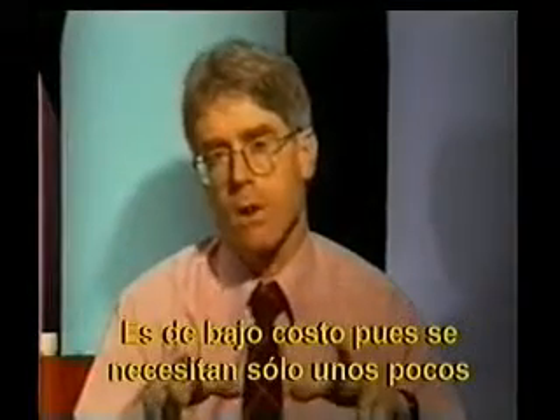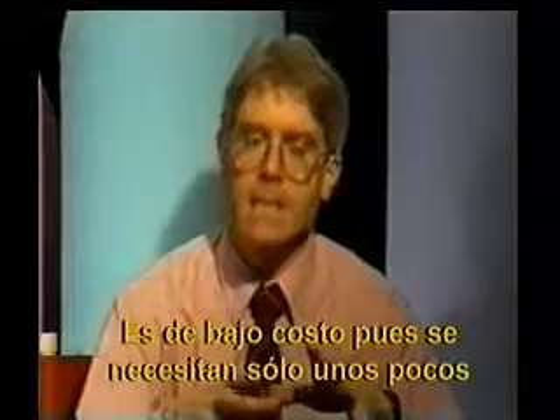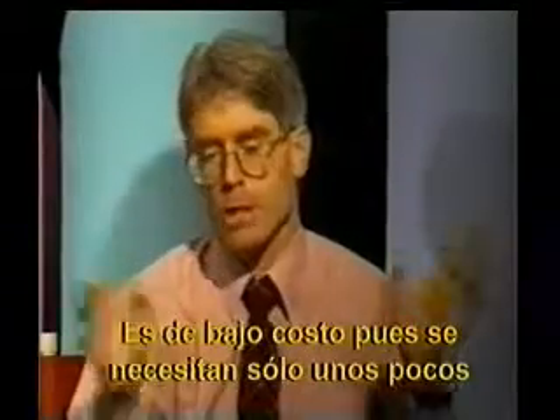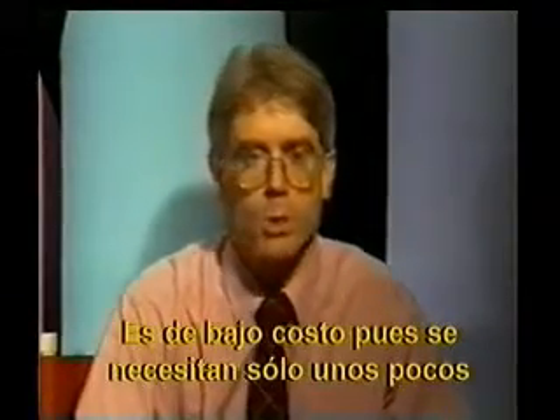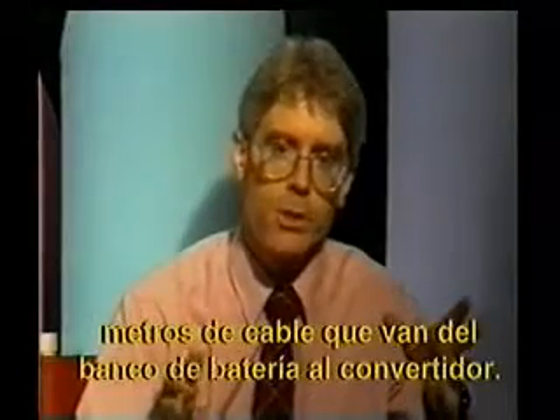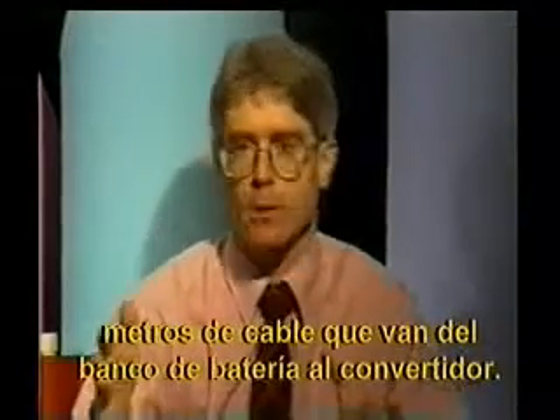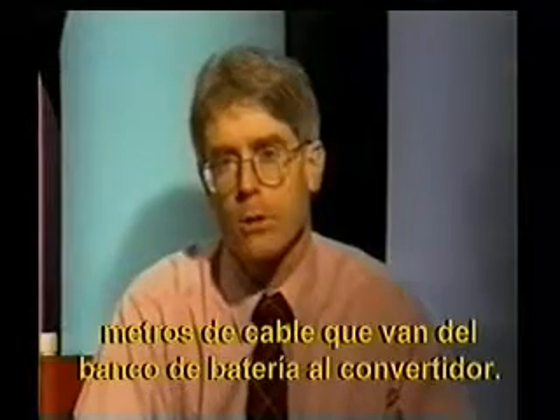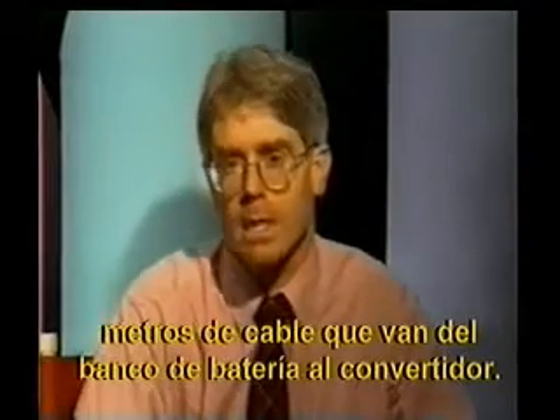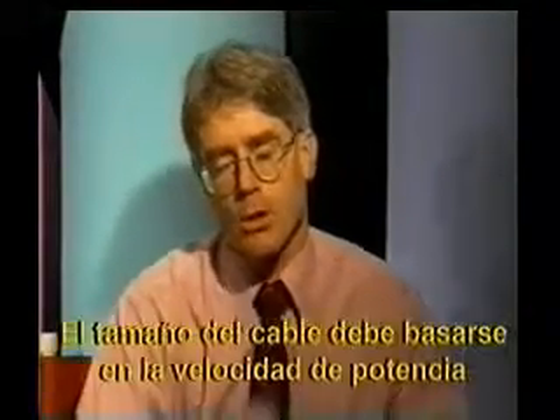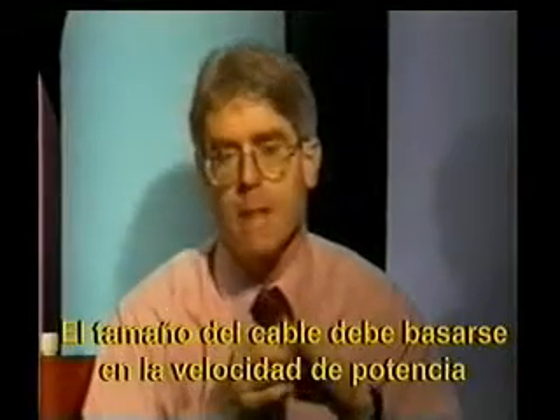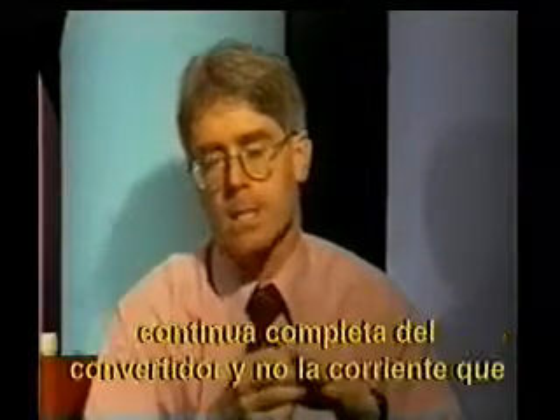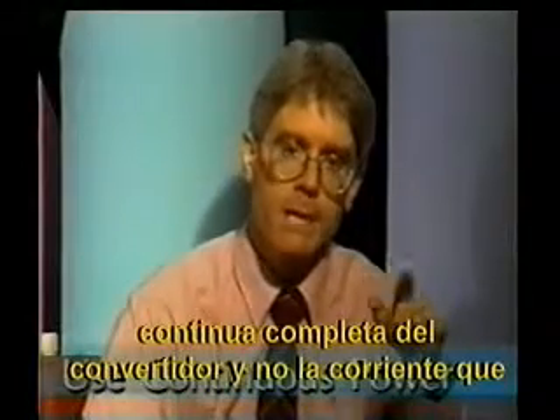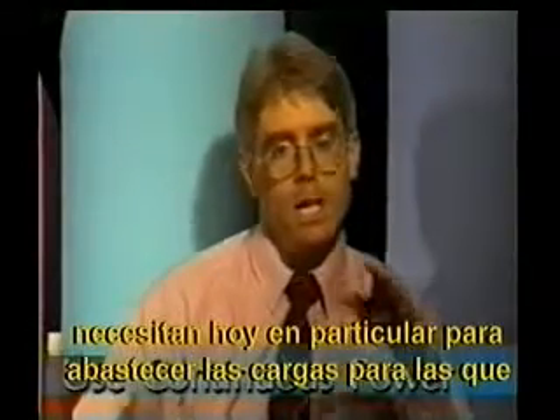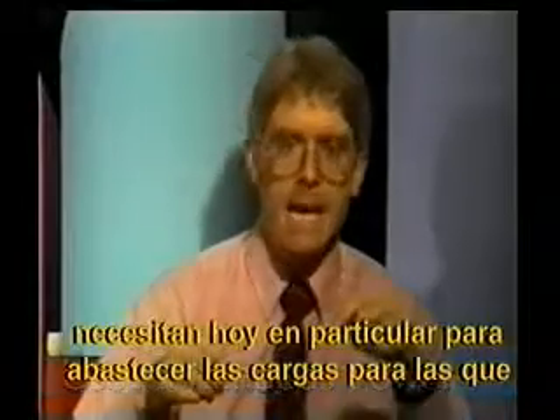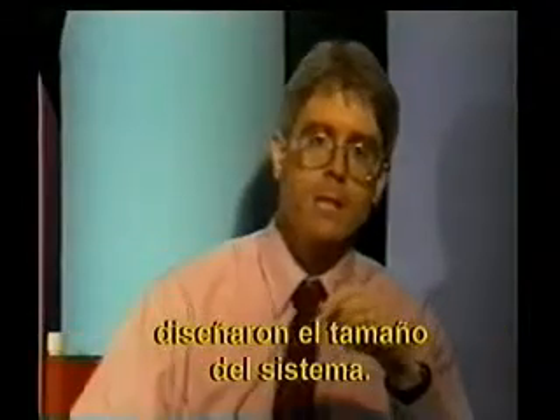The cost involved in using such large wire is actually quite small. You might be concerned that too much expense is going to go into such a large wire, but the typical lengths that are used between the battery bank and an inverter is only a few feet or a few meters. So the total cost of that wire is actually quite small. You should size that wire, that ampacity rating should be chosen based on the full continuous power rating of the inverter, not just the particular current that you need today to meet the loads that you've sized your system for.